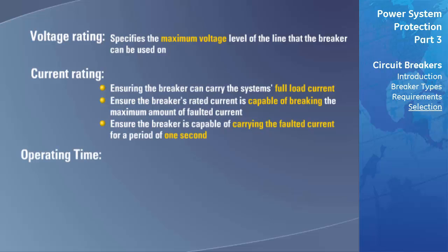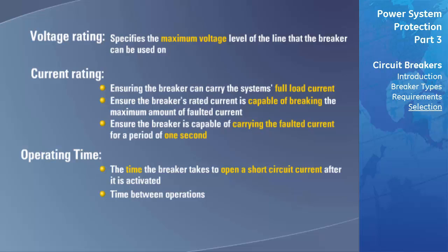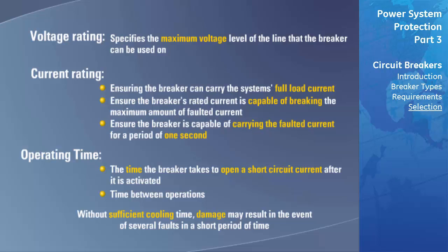Two characteristics of operating time must be observed prior to selection: the first is the time the breaker takes to open a short-circuit current after activation; the second is the time between operations. After a fault is cleared, the breaker is usually significantly heated, and it must be given sufficient time to cool before being closed again. If cooling time is not specified, standard cooling time is approximately three minutes for breakers not intended for rapid reclosing, and 0.3 seconds for those intended for automatic reclosing.